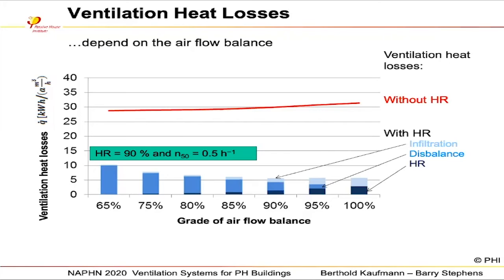This is typically what you have with a passive house, because we are not 100% airtight. Airtightness is 0.5 in this example at 50 Pascal. But if you go down with balance to 95, 90, 85 or so on, you see the infiltration is going a little bit less, but the disbalance effect is going up. And therefore you see 90% balance, so 10% disbalance is, so to say, allowed. You can have it, but going lower is not a good idea.